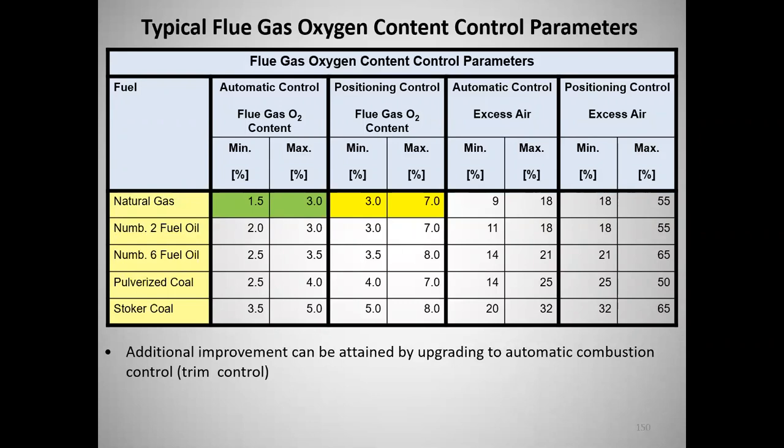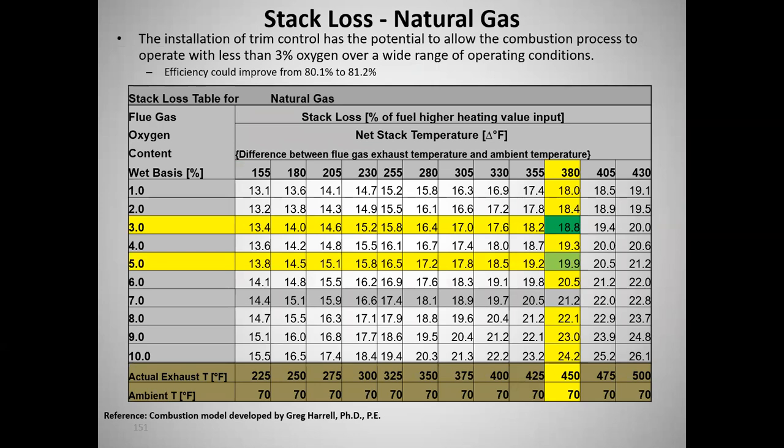Well, let's see. The first thing you would assume is that we did tune it. It's just too compelling not to tune it, too cheap. So we'll base this on assuming we have tuned it and got it down to 5%. But if I go with this automatic control system, I can get it between 1.5 and 3. So we'll make another assumption and rerun this. Not wanting to overstate, I'd rather under-promise and over-deliver on my savings.